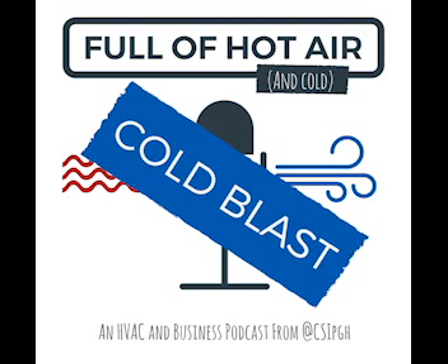So at that point I'm going to say, okay, let's power down. Always be safe when working with high voltage, low voltage, and DC voltage. I'm going to have them disconnect S2 and S3 from the outdoor unit. And what is that doing for them? That's going to eliminate the wiring and the indoor unit out of the equation. So you're just testing whether or not the outdoor is talking to the indoor. Yeah, we're testing to see if the outdoor has the voltage that we need to be able to talk. That's produced on our outdoor PC board. So right now I want to know, do we have the voltage at all?